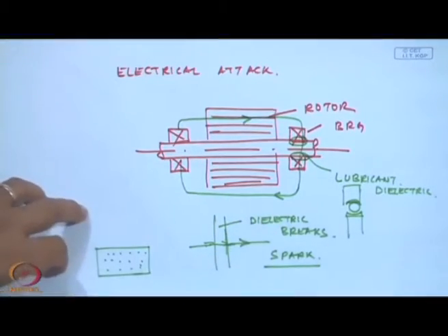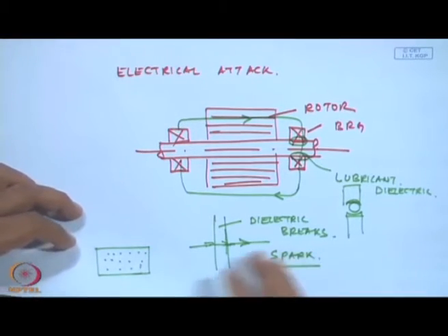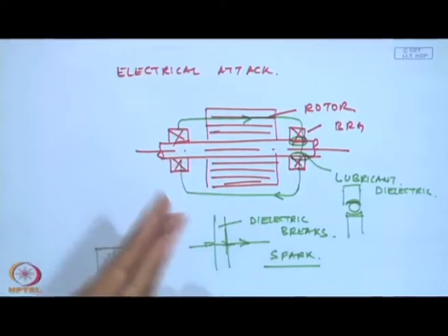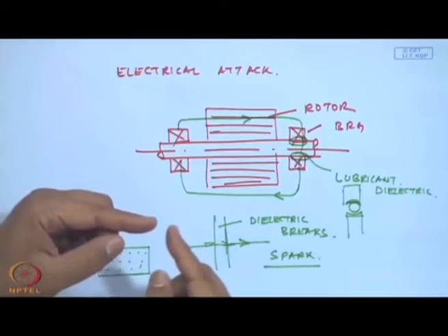So, one has to be very careful when designing electrical motors, or particularly when you have high voltage electricals in your machineries, wherein there are parts with lubricant, and then when there is a discontact. We may not get a voltage as we measure, but when they are going at high speed because of this EMF, if the grounding is not proper, we will get sparks, and these sparks are responsible for erosion, like an EDM, like an electrical discharge occurring. In fact, people use these high voltage sparks in electrical discharge machining to machine surfaces, but here the same EDM may be harmful to our machines.